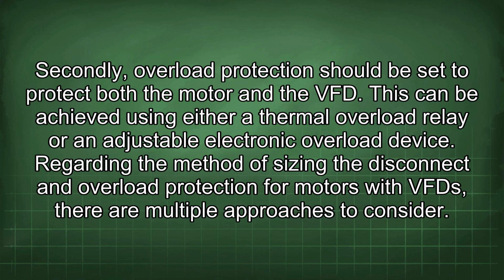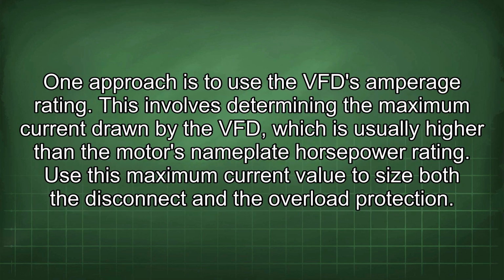Regarding the method of sizing the disconnect and overload protection for motors with VFD, there are multiple approaches to consider. One approach is to use the VFD amperage rating. This involves determining the maximum current drawn by the VFD, which is usually higher than the motor's nameplate horsepower rating. Use this maximum current value to size both the disconnect and the overload protection.